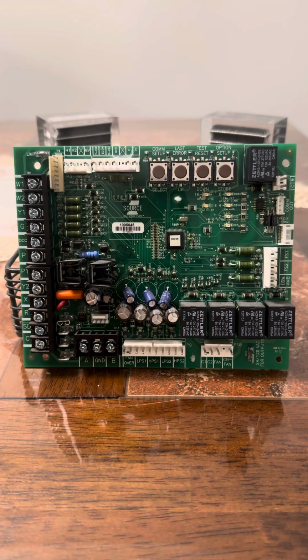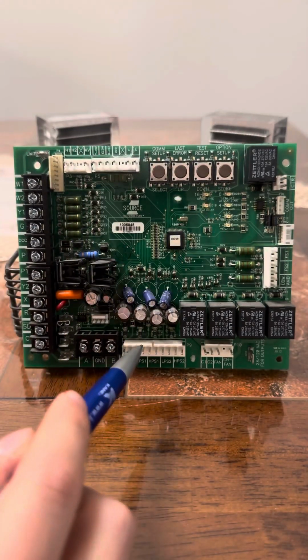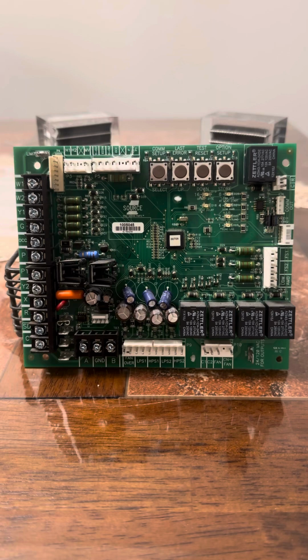Okay. Now, of course, you'd lose 24 volts here most commonly when your filters are dirty or whatever, you trip a limit, right? Whenever the limit is tripped 3 times within an hour, then you're going to lose 24 volts over here. That's going to trigger that 9 flash code, which will lock in the fan. And that's why sometimes you'll go on the roof and you'll find the fan on all the time. But the heating will still run. It will not lock out the heating from this board. It will not lock out this H1 for heating stage 1 output. The ignition board will just automatically, whenever that limit resets, let the heating come back on.